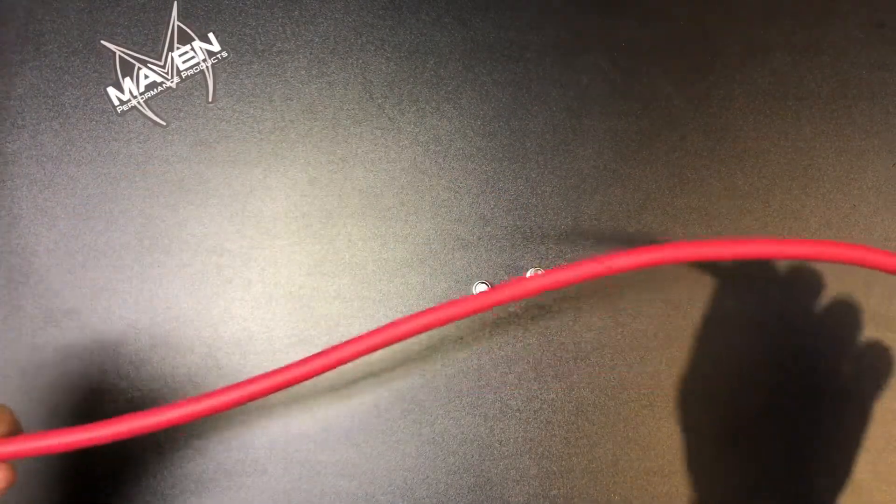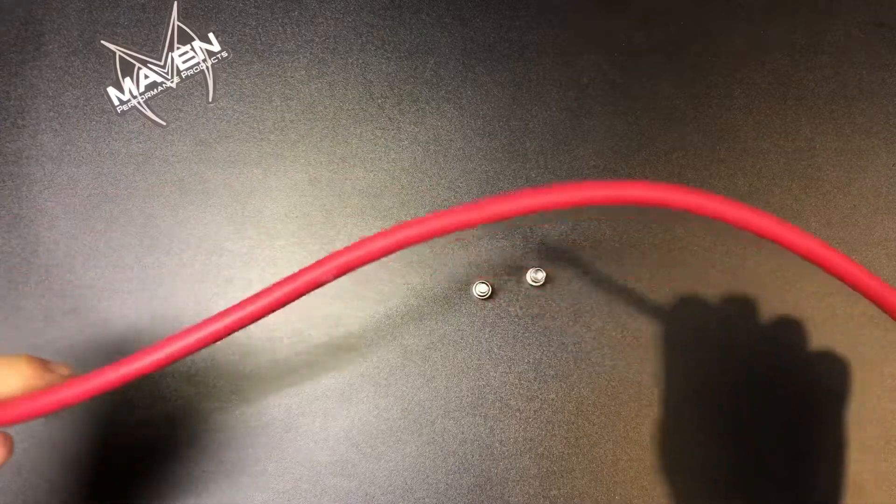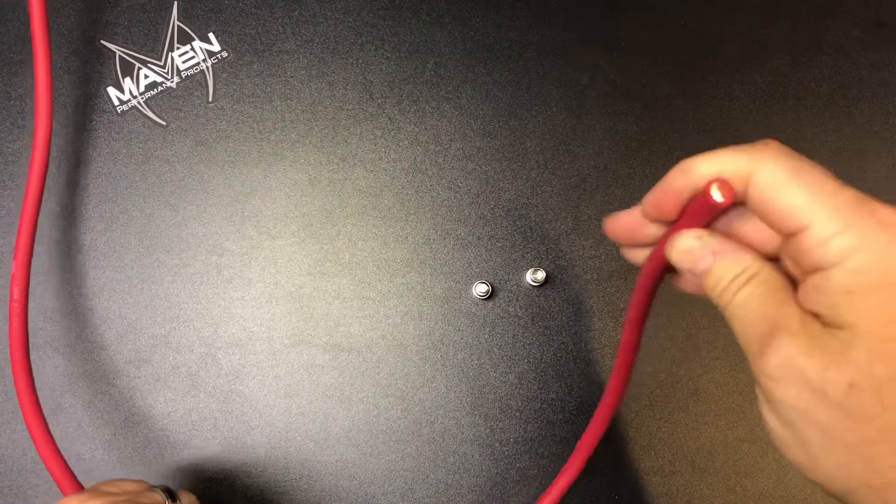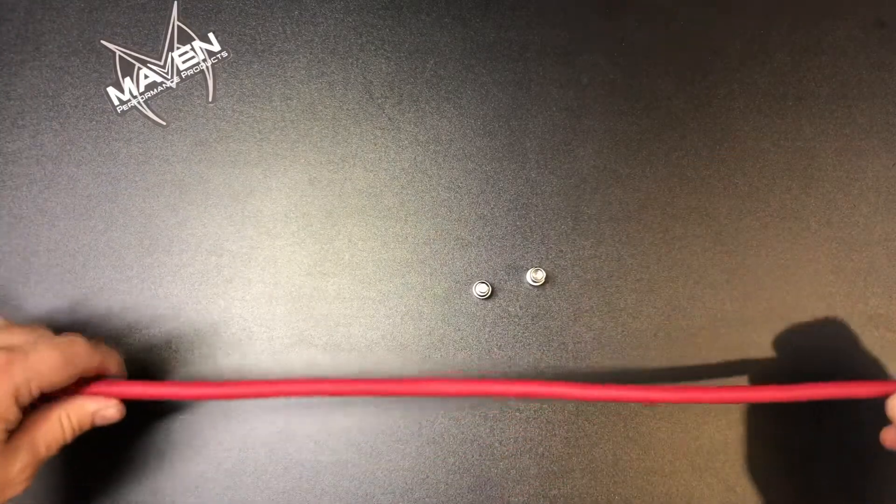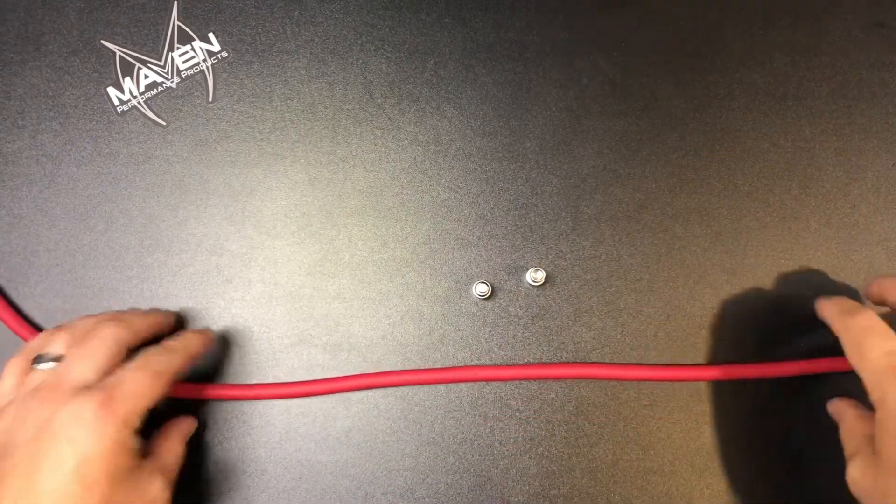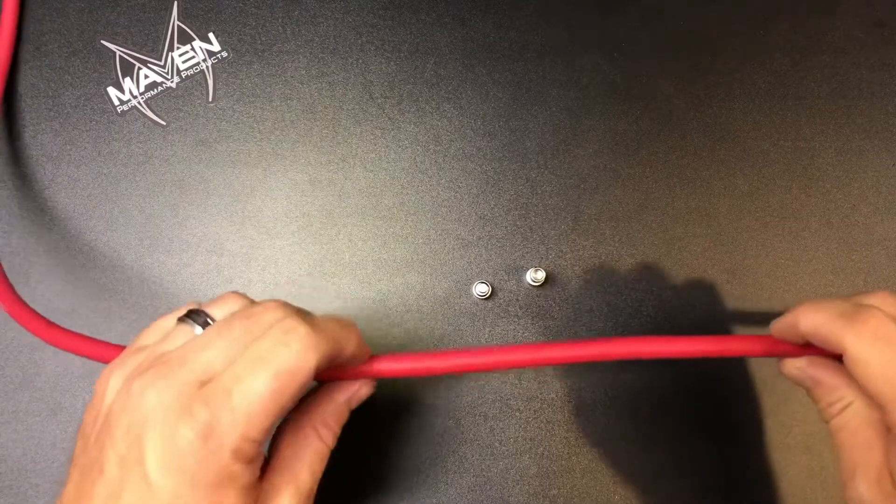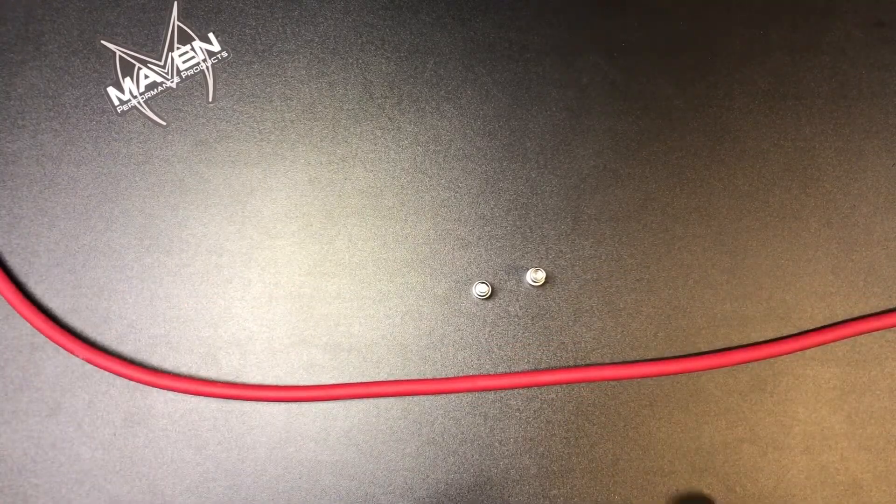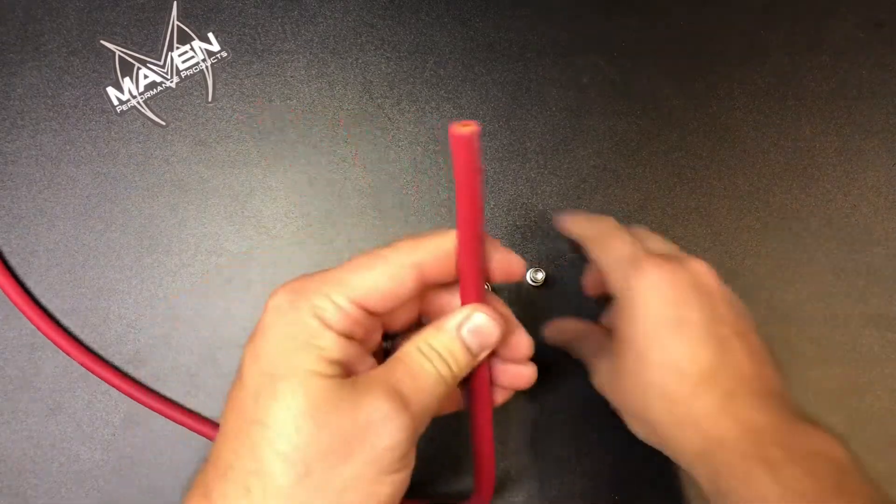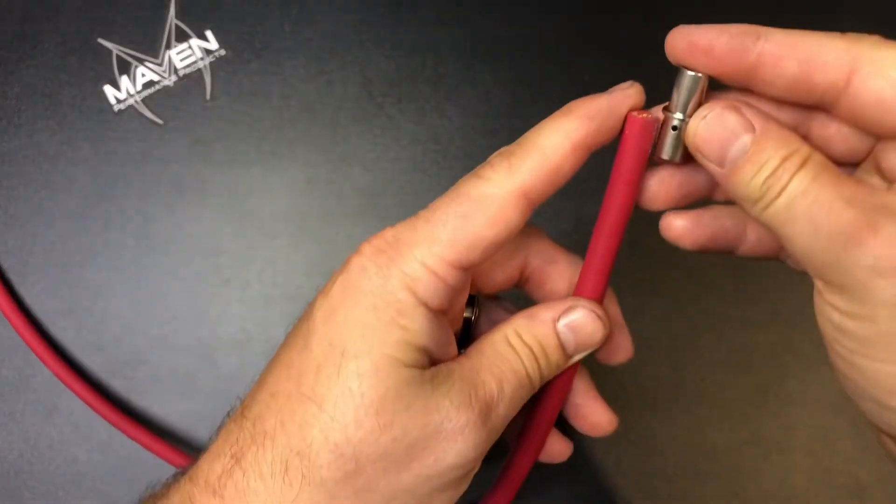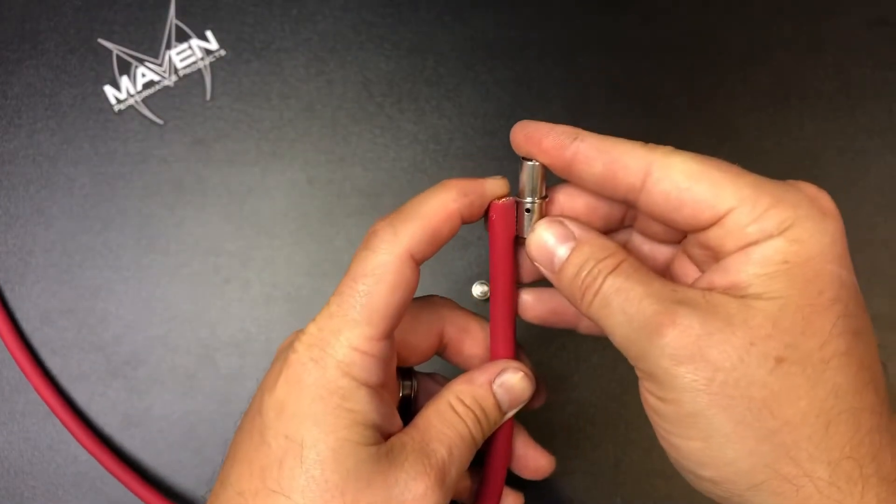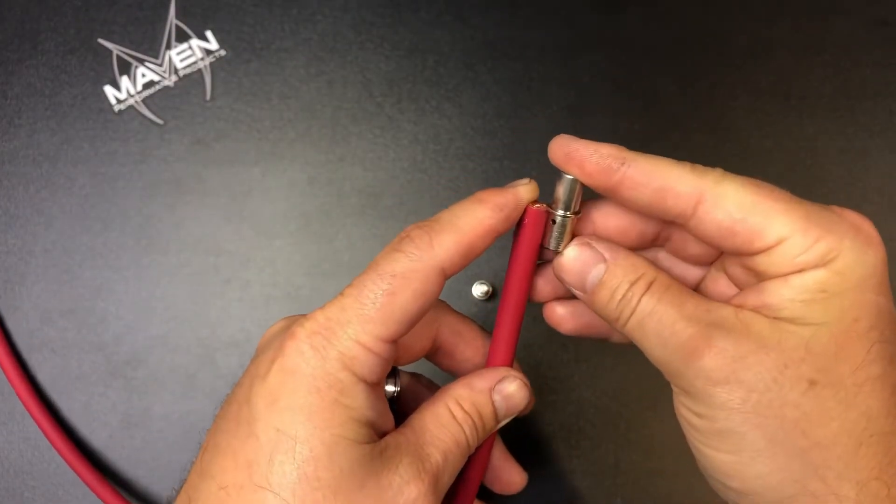Again, this is high quality cable—actually welding cable, very flexible four gauge. If you look, it's got a high strand count with smaller strands, which is generally found in higher quality cable. You'll see they're a little bit smaller diameter than some low quality cable. What we want to do is strip some of the insulation back. You want to strip just a little bit more than you see there, so come down a little bit further so the cabling can be seated completely into the terminal.